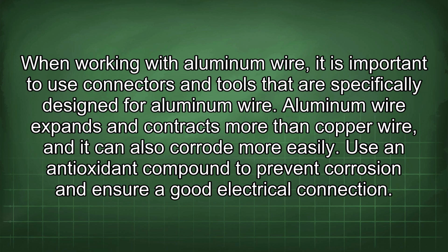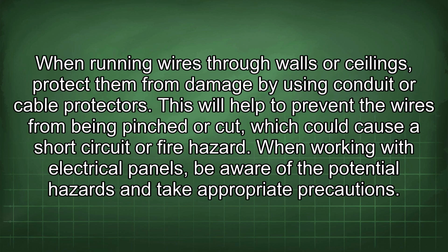When working with aluminum wire, it is important to use connectors and tools that are specifically designed for aluminum wire. Aluminum wire expands and contracts more than copper wire, and it can also corrode more easily. Use an antioxidant compound to prevent corrosion and ensure a good electrical connection. When running wires through walls or ceilings, protect them from damage by using conduit or cable protectors. This will help to prevent the wires from being pinched or cut, which could cause a short circuit or fire hazard.